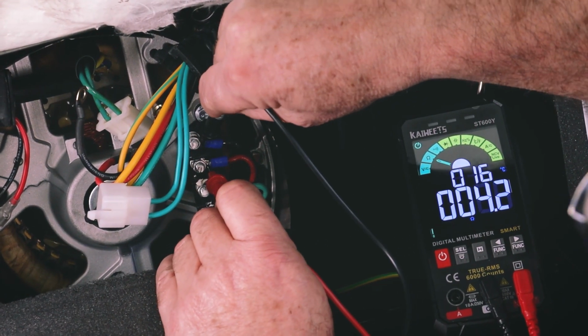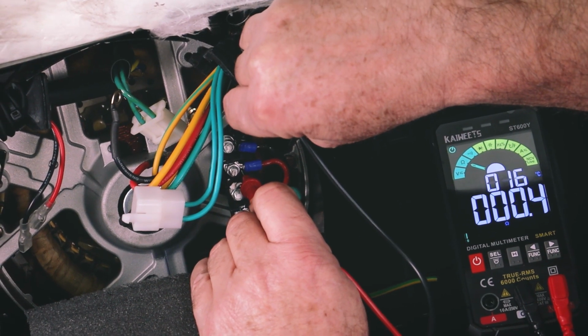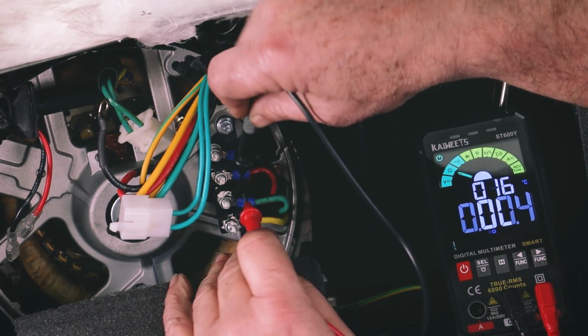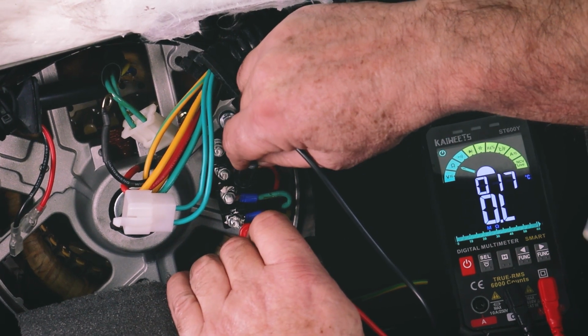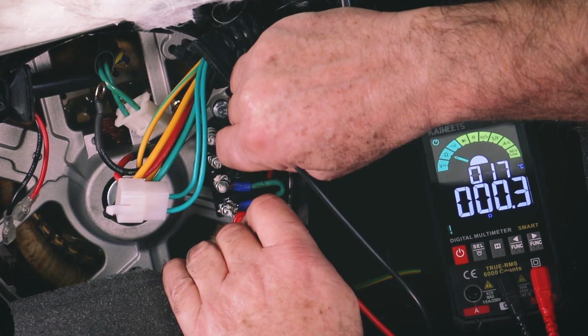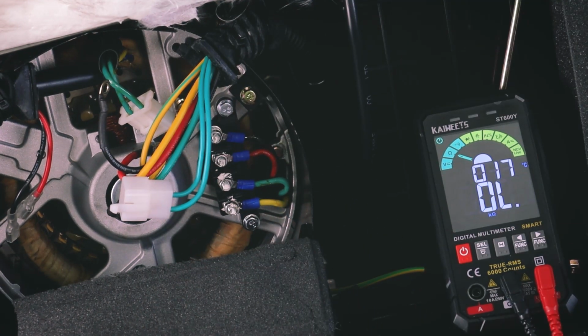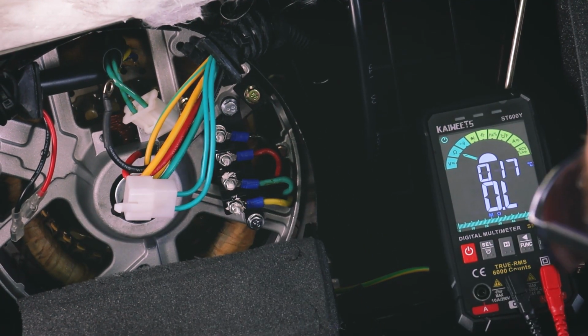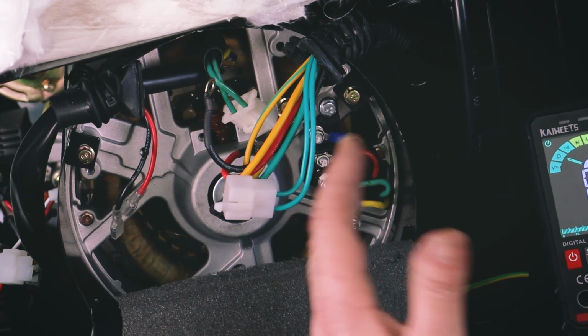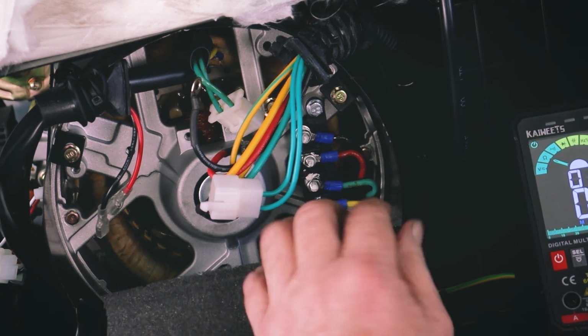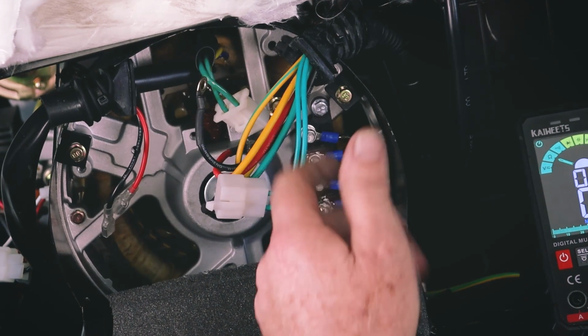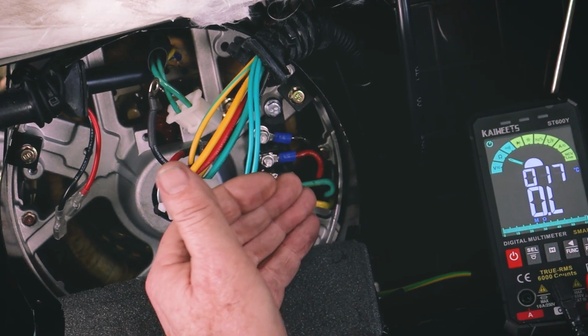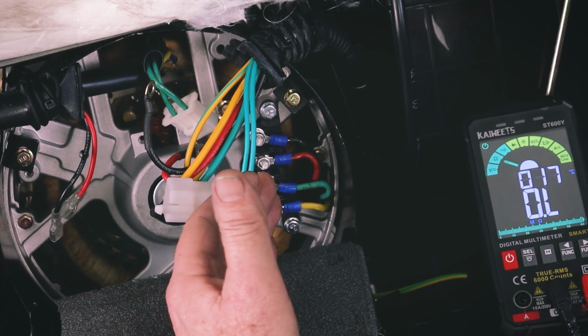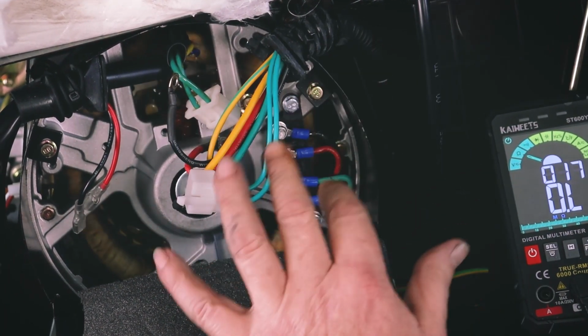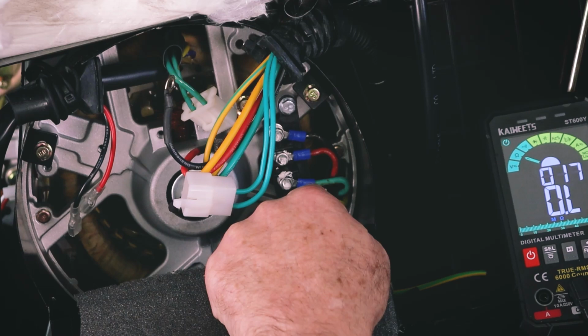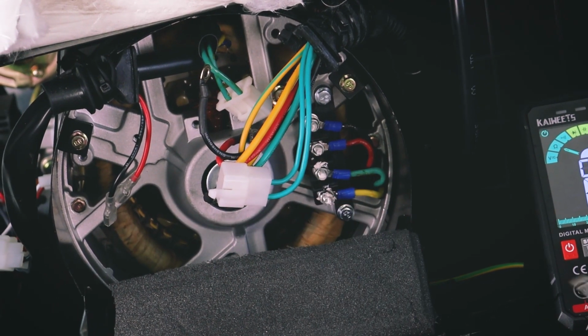So if I go between red and black, I've got 0.4 ohms, very little. And if I go across this winding, 0.3 ohms. Okay, that's the territory we're looking for. You would typically see a small resistance reading. 0.3 ohms, and 0.4 ohms, 0.5. I mean, even up to 1 ohm, but you wouldn't expect 50 ohms or something like that. But that's highly unlikely. Normally the case is that you've got dead open circuit, so no connectivity.